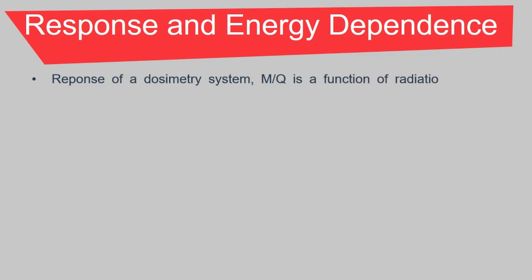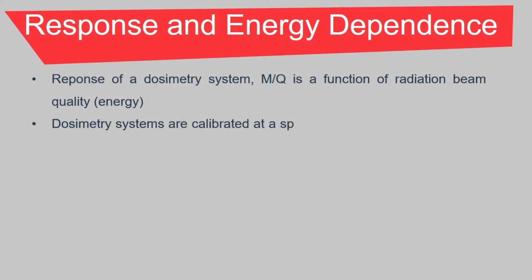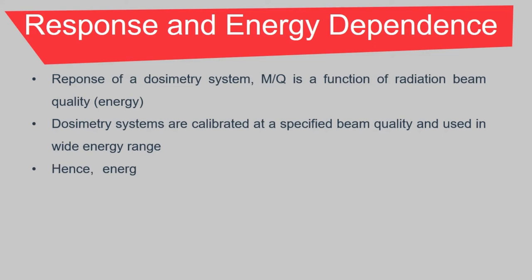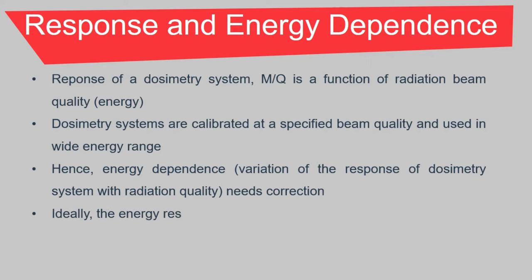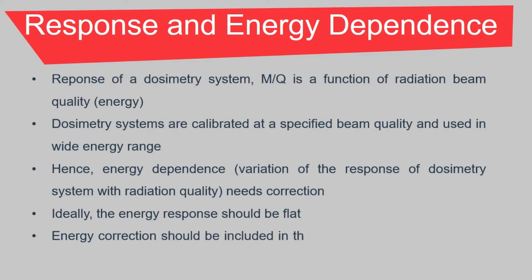The response of a dosimetric system, M over Q, is a function of radiation beam quality, which is energy. Dosimetric systems are calibrated at a specified beam quality and used in a wide energy range. Hence, energy dependence — which is the variation of the response of a dosimetric system with radiation quality — needs correction. Ideally, the energy response should be flat, and energy correction should be included in the determination of the quantity.